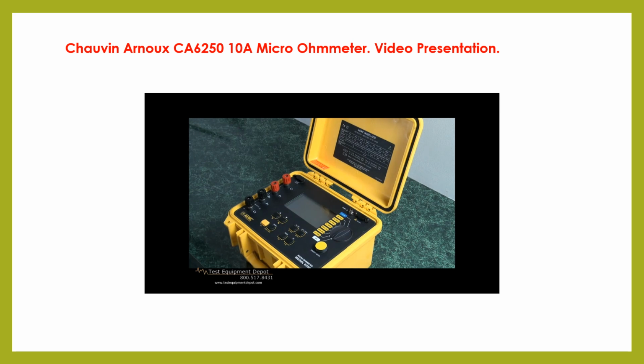It stores up to 1,500 test results. Now, to keep these in neat order so we know where they are and what they are, they will actually increment. They will give us a label of object and a number, and a test and a number. For example, if I was to test a 3-phase transformer, I would call that transformer object number 1, and as I tested A phase, that would be test 1, B phase would be test 2, C phase would be test 3, for example. And I can store 1,500 sets of those readings.